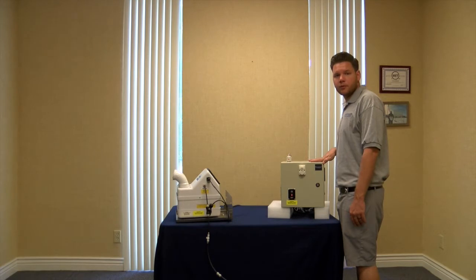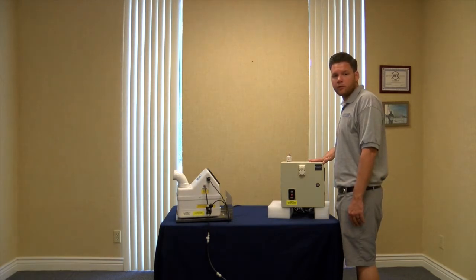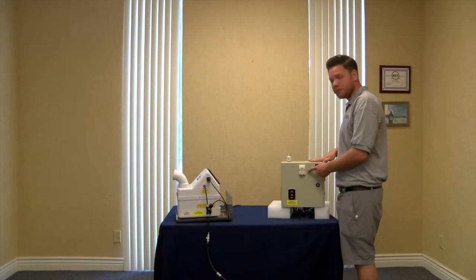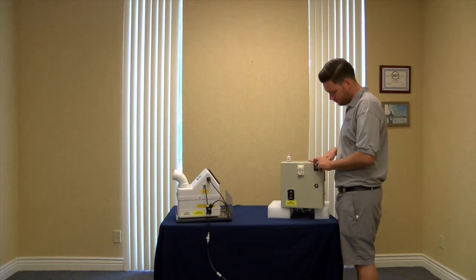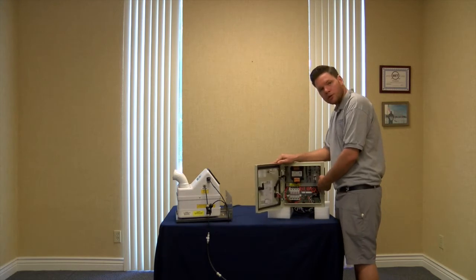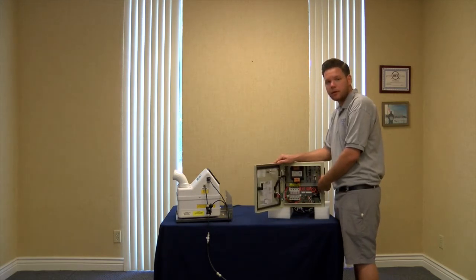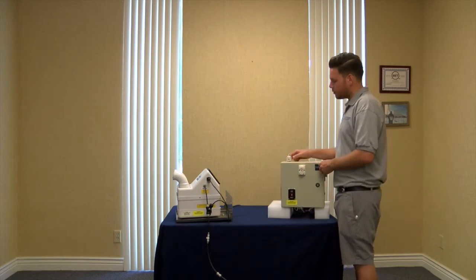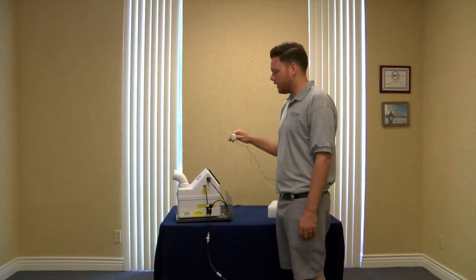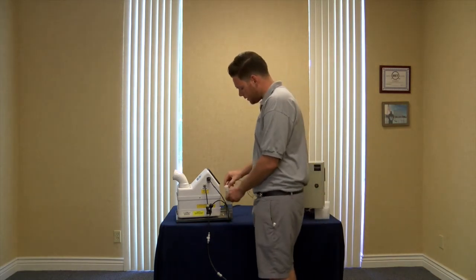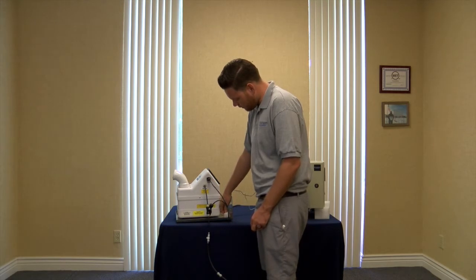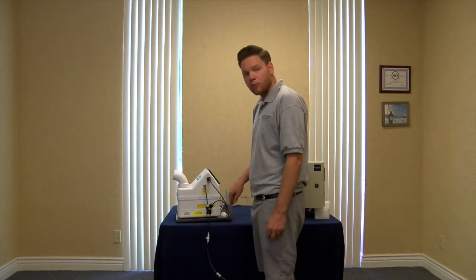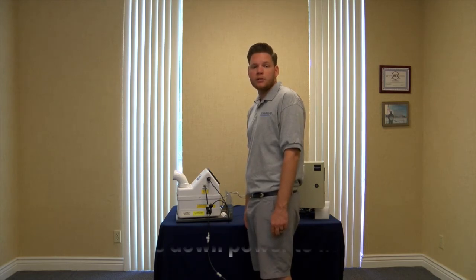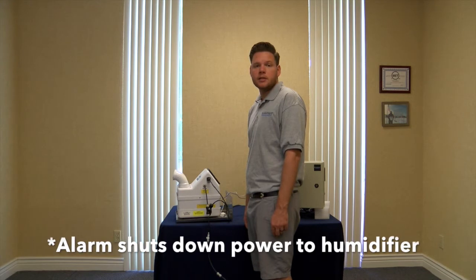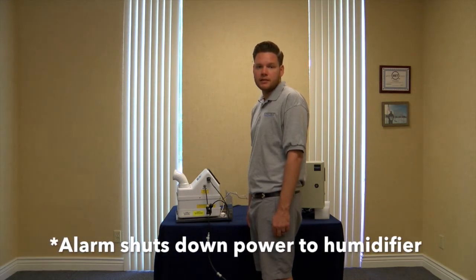This unit is equipped with our optional WaterGuard Overflow protection. This option features an audible alarm, the WaterGuard sensor, and the WaterGuard control unit located on the inside of your control panel. For this option, simply take the provided WaterGuard sensor and place it in the shelf. It will sit in the shelf, and when an overflow happens, it will cause the audible alarm to trip, disengaging your 24 volts VAC inside the unit.